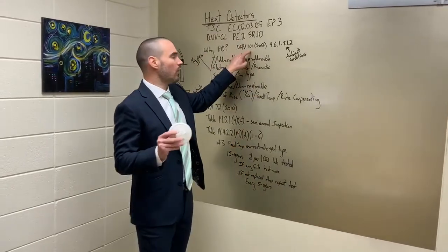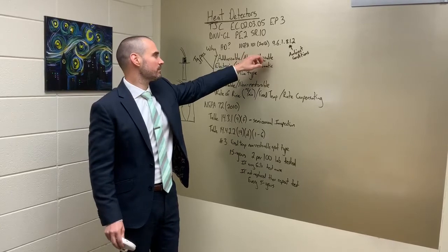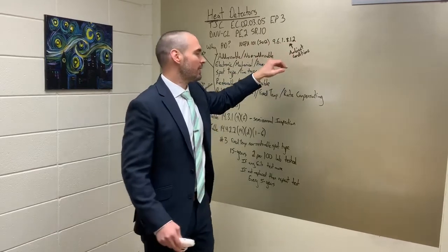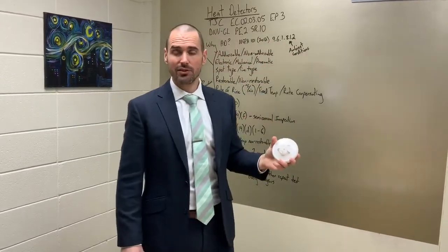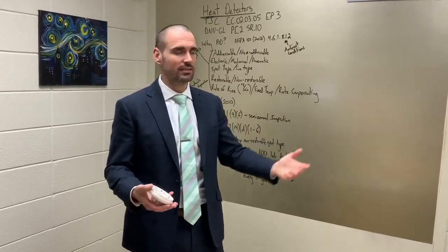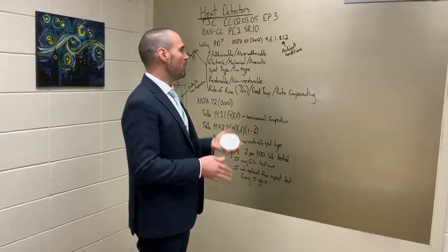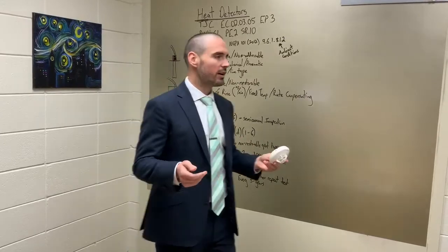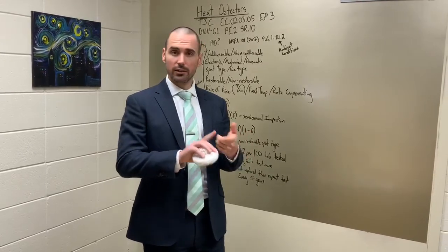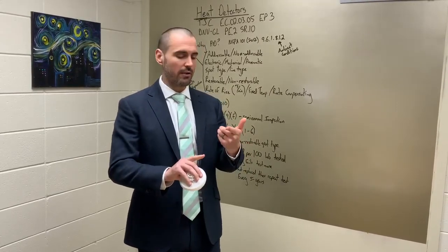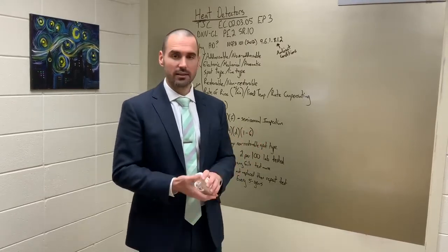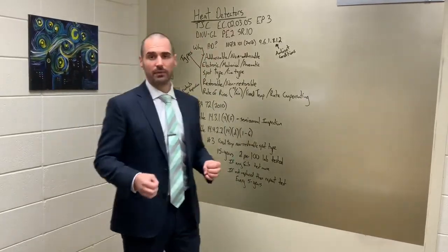Code NFPA 101, the 2012 edition, because that's CMS adopted, Section 9.6.1.8.1.2 tells us that we can use heat detectors when the ambient conditions for smoke detectors aren't good due to dust or humidity. Where in a hospital are you going to find those? Primarily central energy plant, elevators—it's actually required in elevators if you have a sprinkler head—mechanical rooms, storage rooms, anywhere that's really dusty that can cause a lot of false alarms.